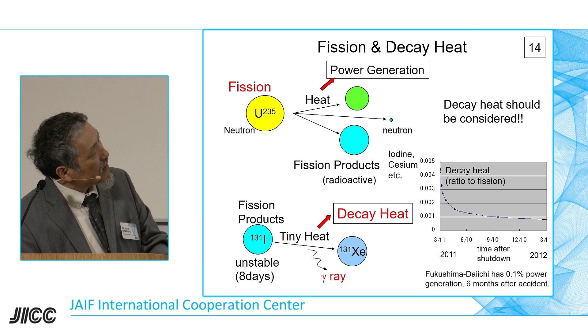This is very significant. For example, with 1 gigawatt of energy generated, after half a year we may still have 1 megawatt remaining from that 1 gigawatt - that's just one-thousandth. So for a 1 gigawatt reactor source, 1 megawatt of decay heat should still exist just after 6 months. And even after 1 year, we still have 0.08% - anyway, a huge amount of energy is still being generated by this decay heat.